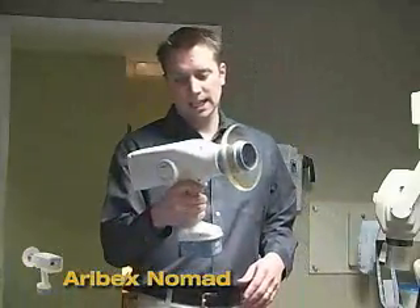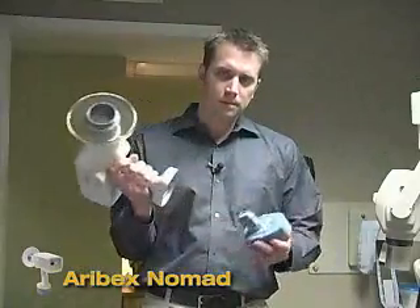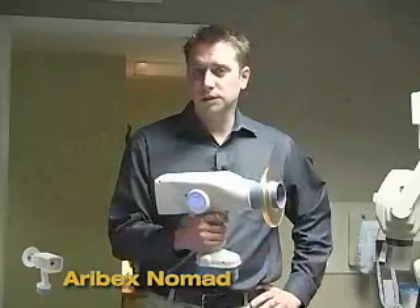The traditional use of these swing arm x-ray generators has changed with new technology from Aribex. It's called the Nomad, and it's a portable x-ray generator that fits in the palm of your hand. It operates with an 18-volt battery and delivers 60 kVp of true DC power.